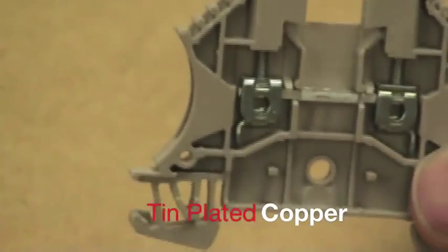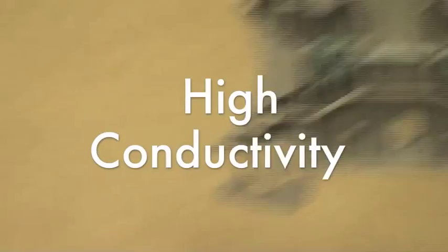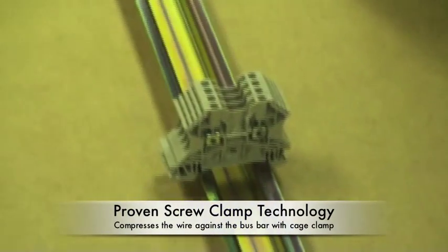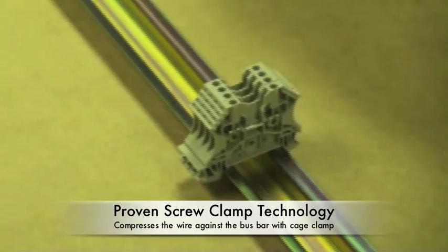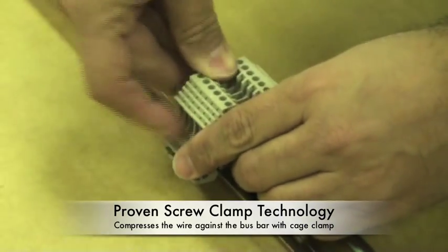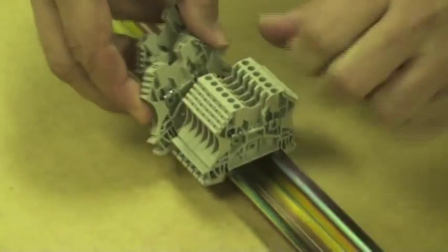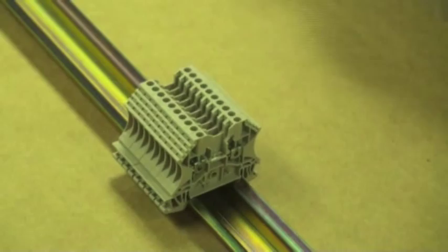The current bars are constructed of tin-plated copper to ensure high conductivity and corrosion resistance. The Weidmuller W-series terminal block product line employs the well-proven screw clamp technology that compresses the wire against the bus bar by using a cage clamp constructed of hardened steel. The special design of this clamp provides exceptional contact force as well as vibration resistance.